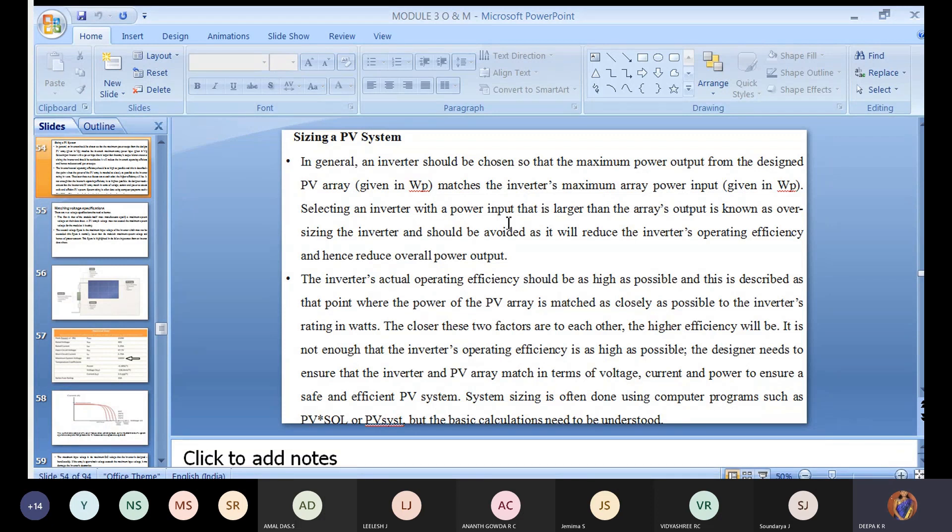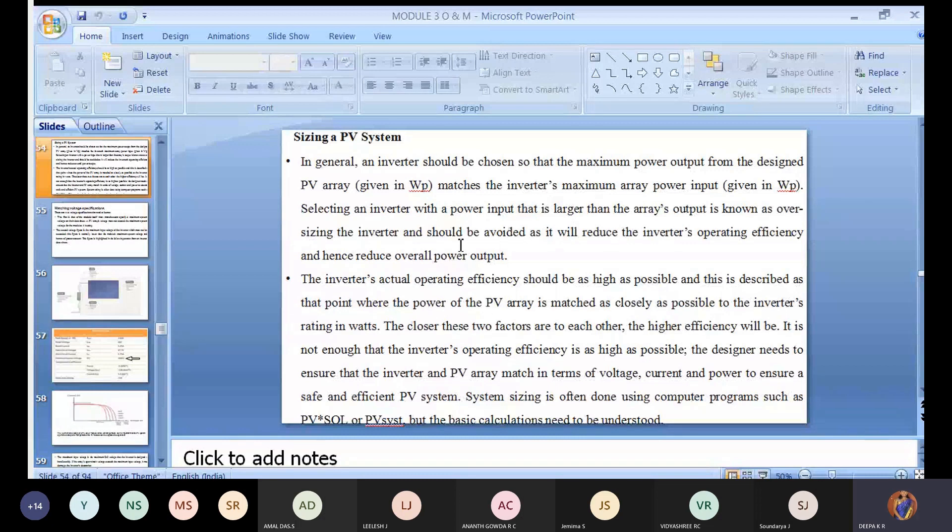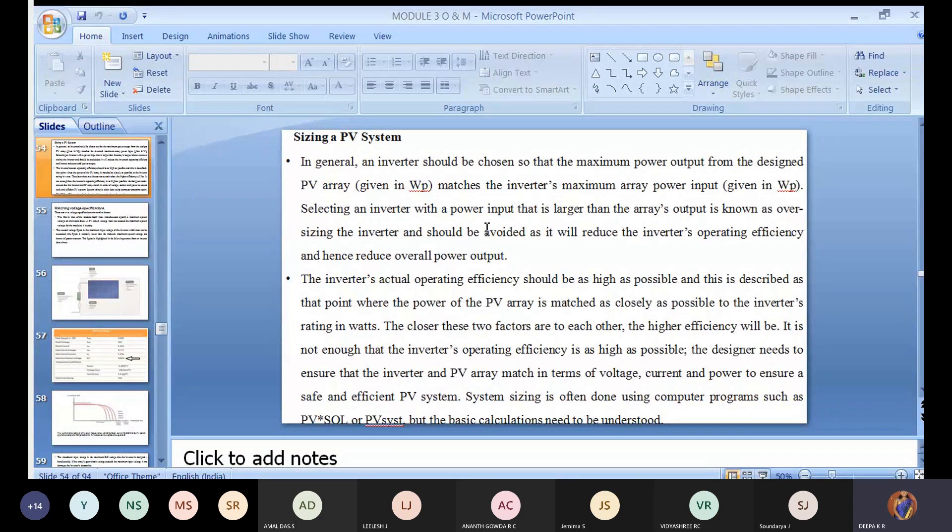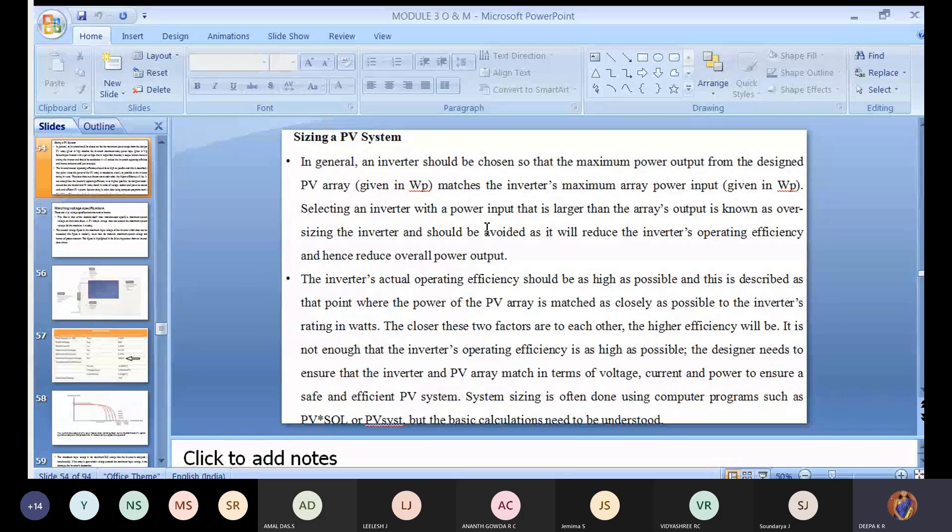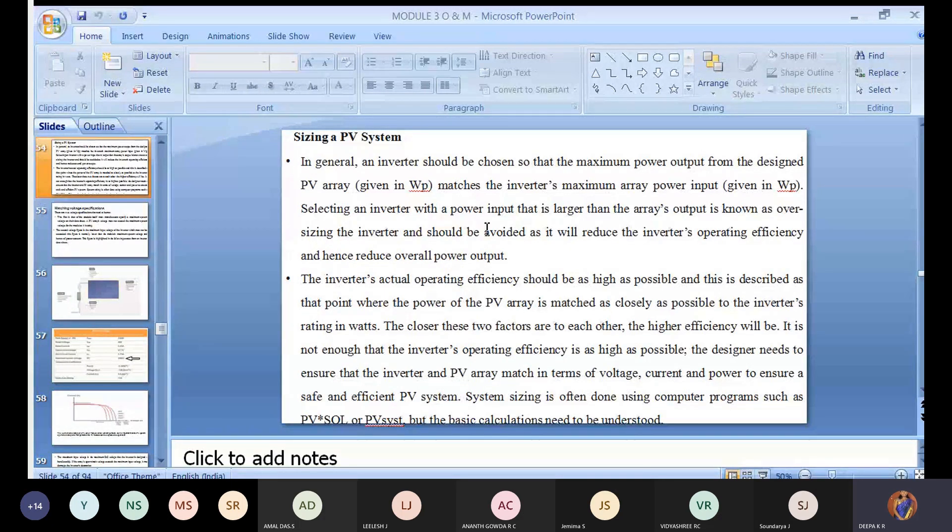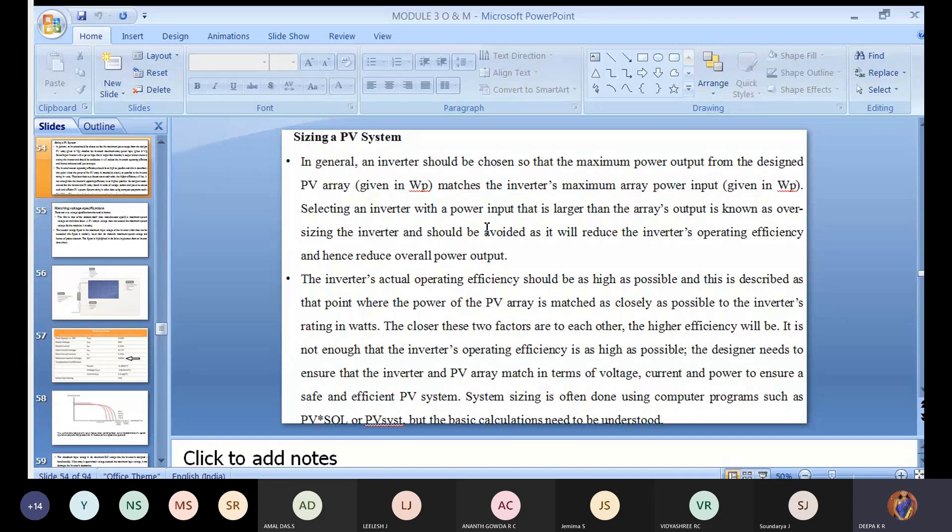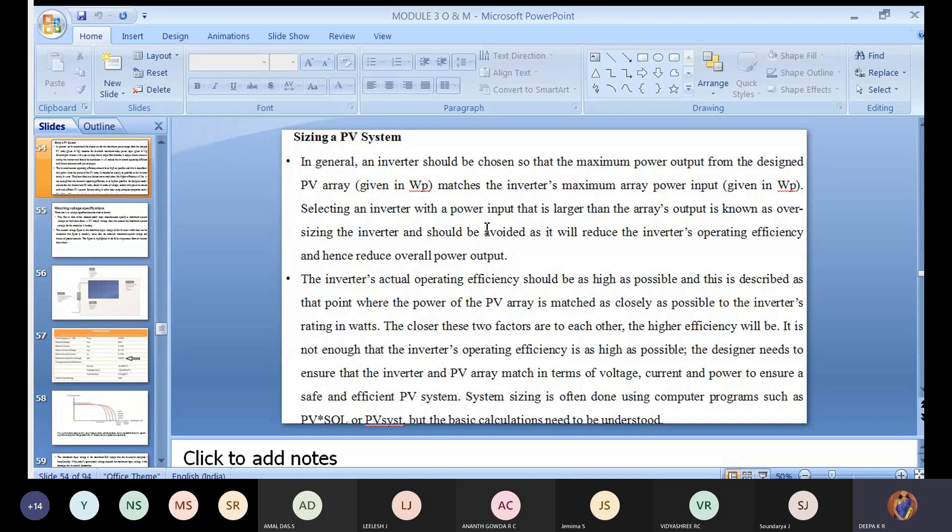Selecting an inverter with a power input larger than the array output is known as oversizing and should be avoided as it reduces the inverter operating efficiency and hence reduces overall power output. This is like over-smartness. You know the capacity and output of PV panels - how many modules you're placing, how much DC voltage you're getting. After converting, how much AC you're getting - everything you know before installing itself. You have to choose the proper inverter. If your current rating is 4.5, choose an inverter rating of 5 amps. Why go for 10 amps?